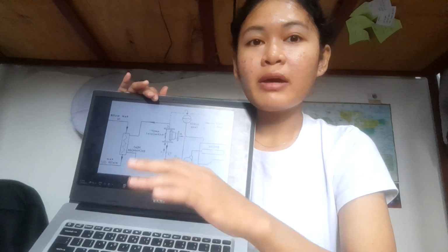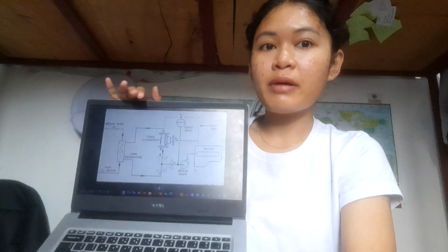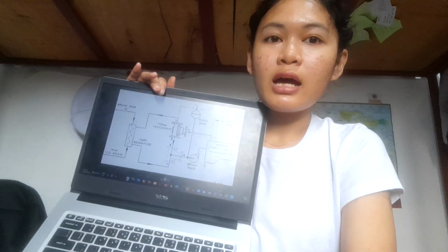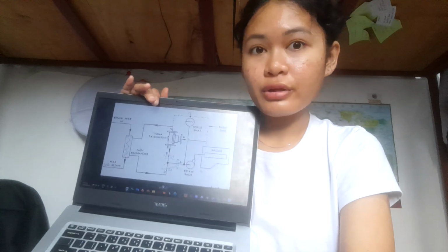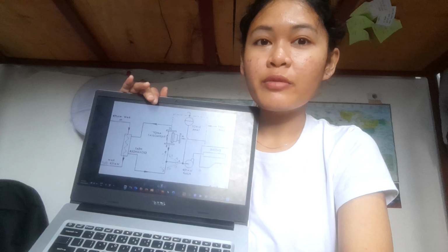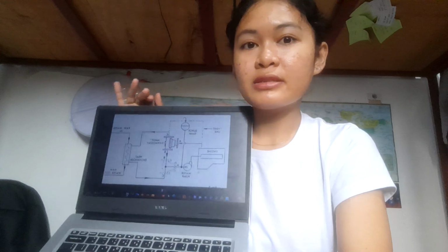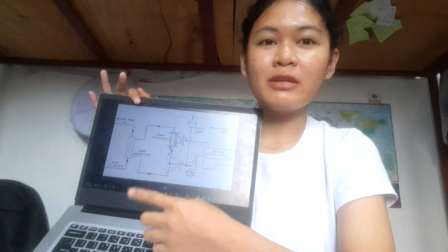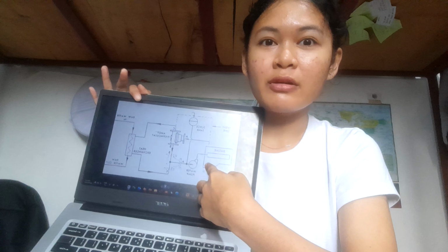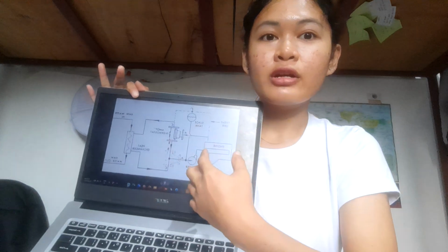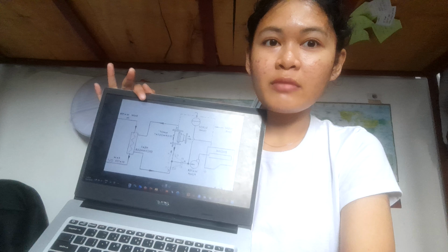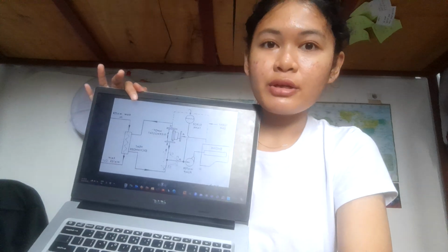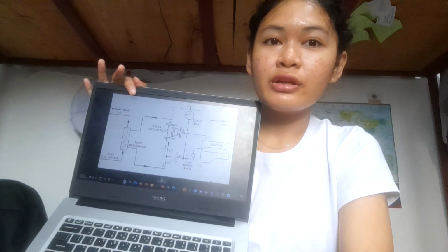As for the bypass flow, the water that goes through the bypass line is not cooled. The two flows, the cooled water from the heat exchanger and the warm water from the bypass, are mixed together. The water in the bypass does not go directly to the engine because they will mix together before reaching the water pump. The mixing action results in a stable and consistent temperature for the water entering the pump.